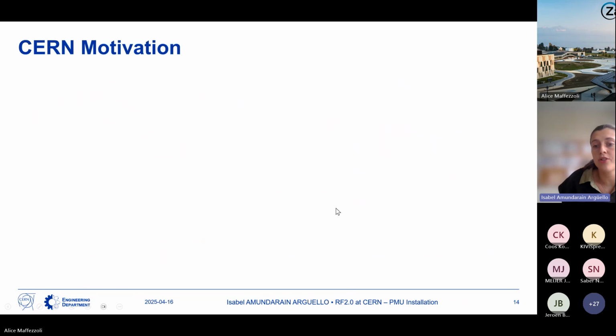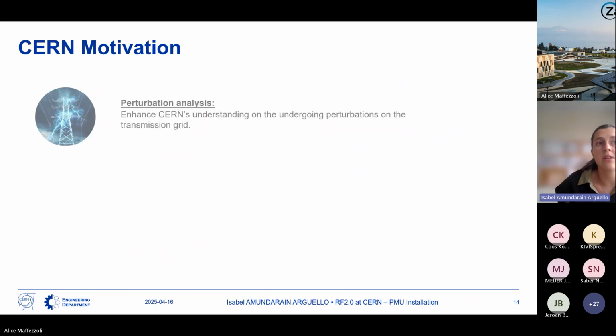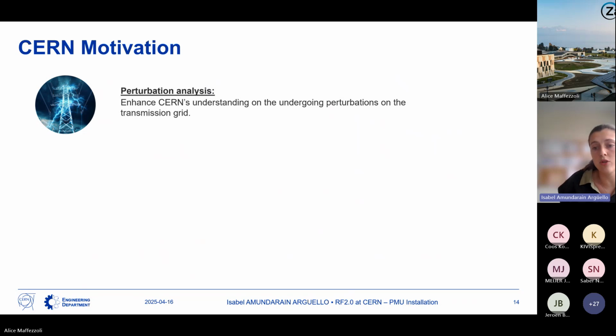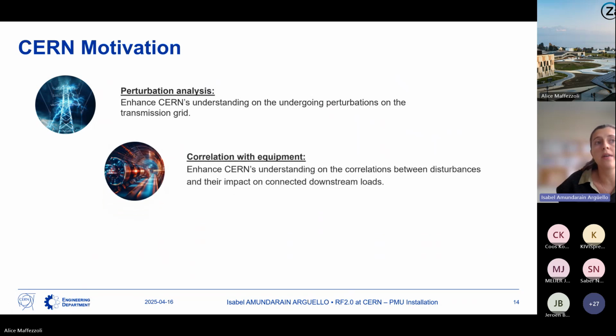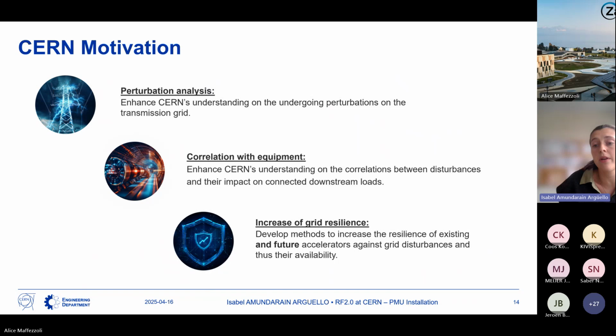Regarding CERN's contribution to the RF 2.0 project, the electrical distribution systems in particle accelerators, and at CERN too, typically use standard SCADA systems which have slower dynamics. That's why deploying the PMUs will benefit us, starting with analysis of perturbations coming from the upstream electrical transmission grids, better understanding how those perturbations impact our equipment and different subsystems and components, increasing grid resiliency by addressing specific weak points, and providing guidelines for future accelerators, in particular for the FCC, the Future Circular Collider.